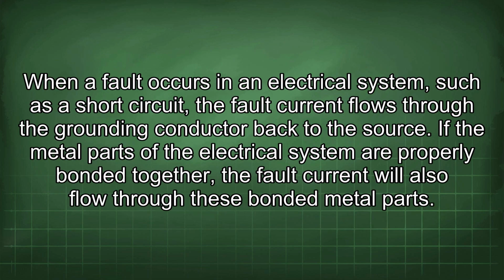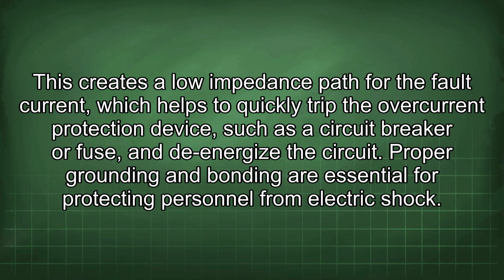When a fault occurs in an electrical system, such as a short circuit, the fault current flows through the grounding conductor back to the source. If the metal parts of the electrical system are properly bonded together, the fault current will also flow through these bonded metal parts. This creates a low impedance path for the fault current, which helps to quickly trip the overcurrent protection device, such as a circuit breaker or fuse, and de-energize the circuit.